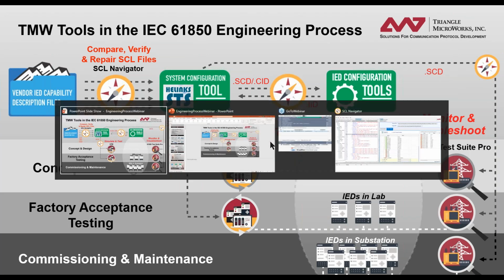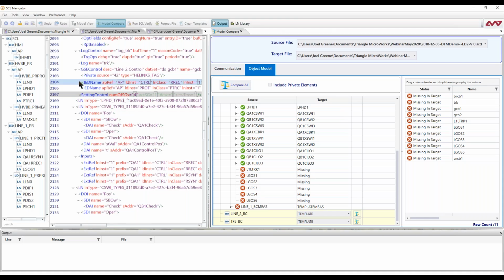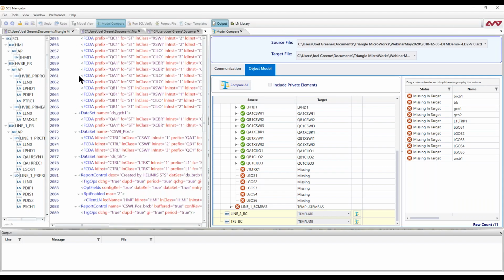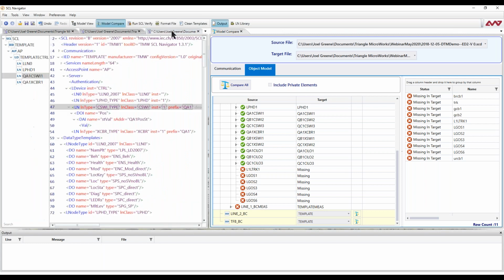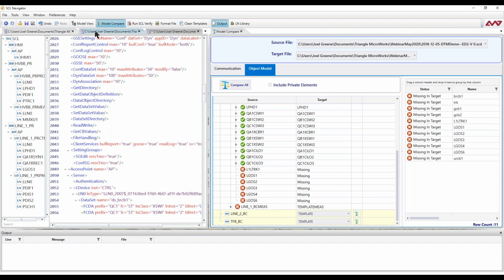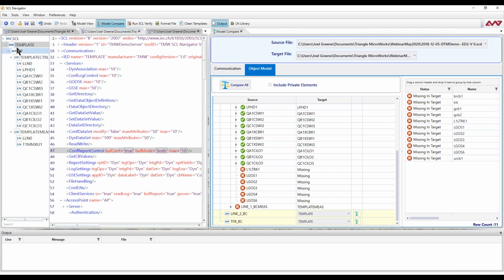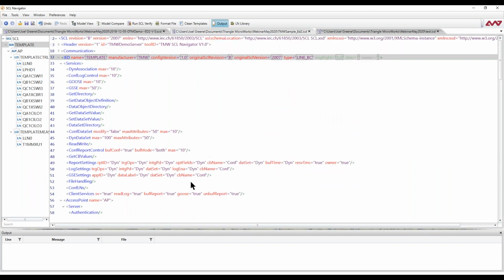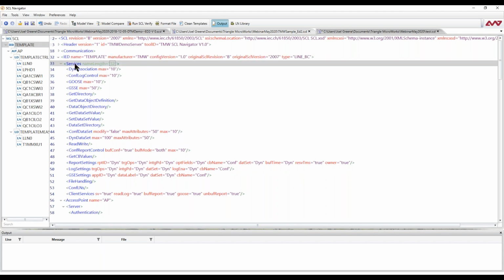We are currently in the working group discussing some extensions to the standards that would allow to create what we call an ISD or IID specification description file. And with that, we could express also service requirements. Currently, that's not yet directly available in the standard as such. Of course, you can use the approach of a virtual IED to do something similar. And then the tool basically will need to compare the required services against what is offered from the IED.